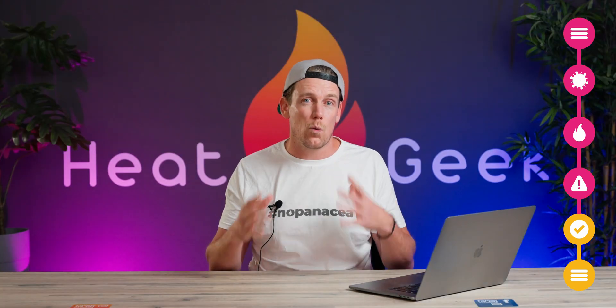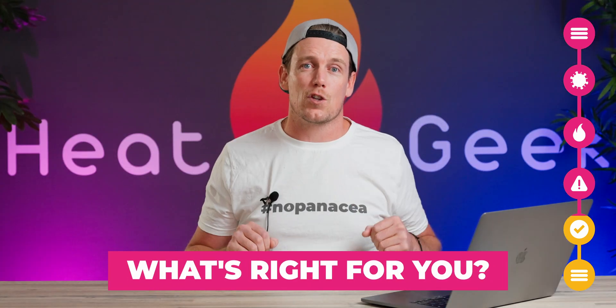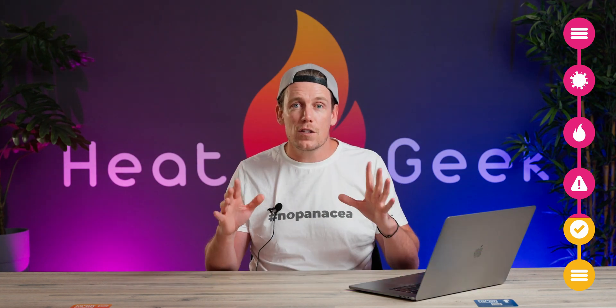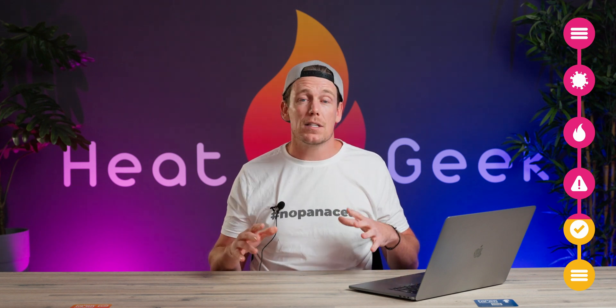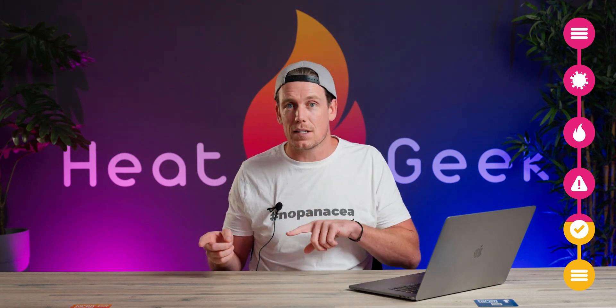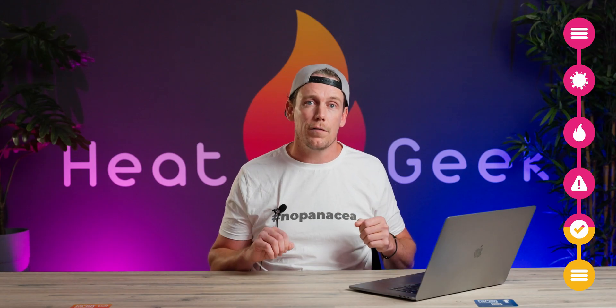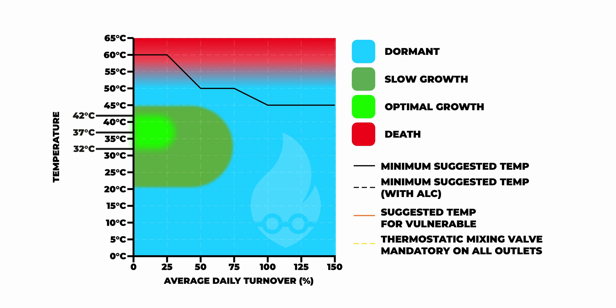Using anti-Legionella cycles may even persuade you to keep your cylinder cooler during the week. Be aware though — if you find that you run out of hot water you may need to bump it back up a bit. So for your specific situation, the name of the game is to keep the store temperature as low as possible while keeping safe. The vast majority of homes will be fine at 50 degrees, but if you want to increase the efficiency of your gas boiler or the SCOP of your heat pump, take another look at this graphic. Once your average daily turnover is above 100%, we don't see much of an issue with a minimum store temperature of 45 degrees. If you follow the black line on this graph you will see the minimum temperatures we suggest, and the dotted line shows the minimum temperatures we suggest with anti-Legionella cycles.